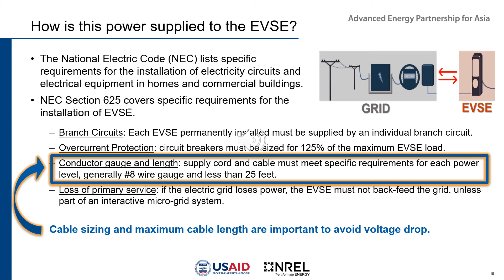NEC requirements, as well as common electrical equipment ratings, have a strong influence over installation practices and EVSE options. For instance, portable level 1 units typically operate below the maximum permitted power, such as 12 amps for a power of 1.4 kilowatts. This is because they typically plug into 120 volt receptacles on a circuit where other devices may be operating. If these devices were too powerful, it could trip the circuit breaker and turn off the lights and devices in that room.